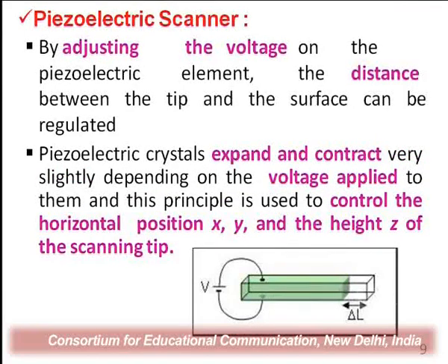By adjusting the voltage on the piezoelectric element, the distance between the tip and the surface can be regulated, and this can work in all directions, X, Y, and Z. As we see in the diagram, the piezoelectric crystal extends and contracts very slightly depending on the voltage applied to it, and this principle is used to control the horizontal positions X, Y and the height of the scanning tip.